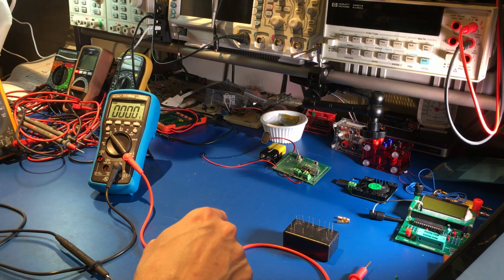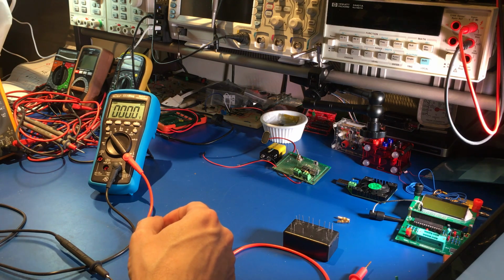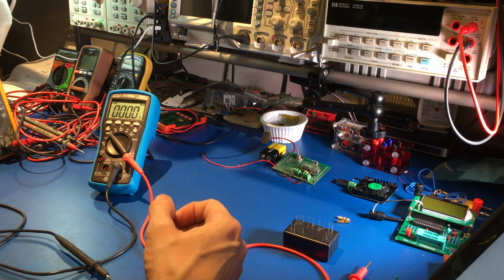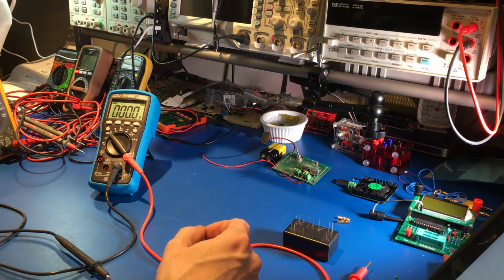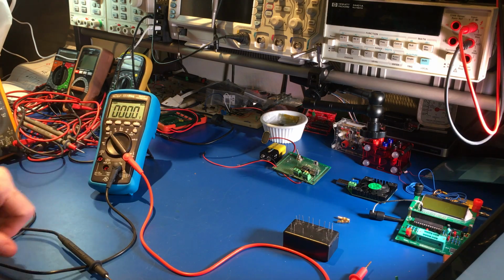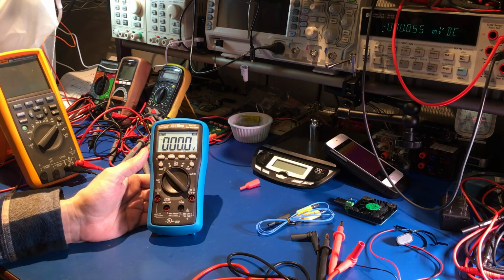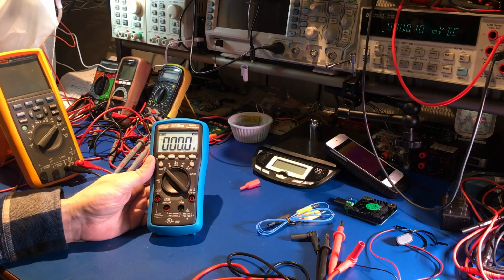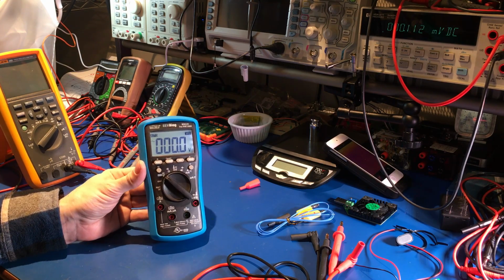The VFD actually stands for variable frequency drives. This enables a digital low pass filter to filter out some of the noise when you're reading your voltage or your hertz in a noisy AC environment. So that's actually a low pass filter. It's a digital low pass filter that's enabled on the VFD, which is a nice little feature too as well. And if you hold down your select button, there is your backlight, and that is a really nice, clean, well lit backlight.